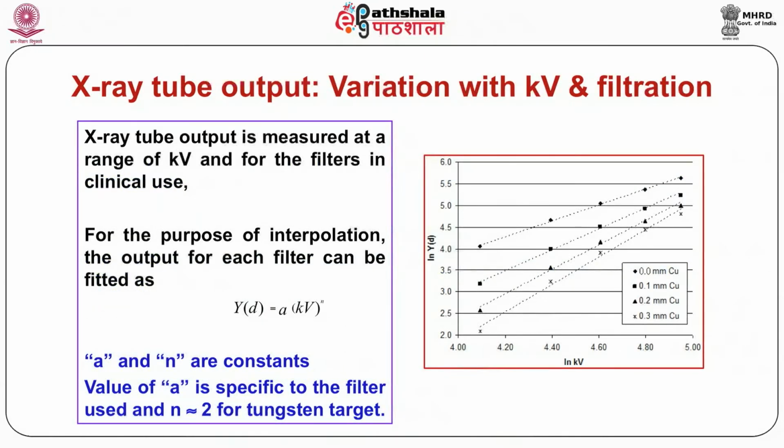A typical setup for measurement of X-ray tube output using a calibrated solid state dosimeter, which has lead backing to reduce backscatter, has been shown in the figure. The dosimeter and its control unit are also shown in this figure for demonstration purpose only, and in actual situation the dosimeter control unit is kept in the operator area inside the protective lead barrier.